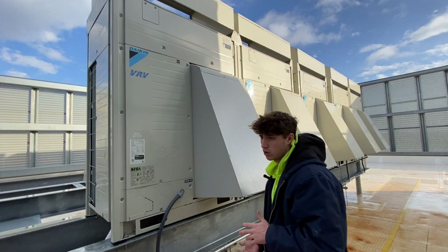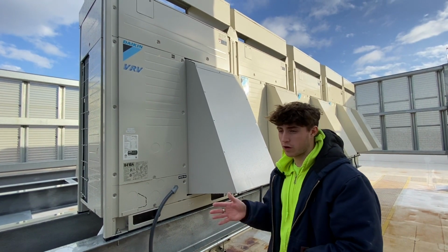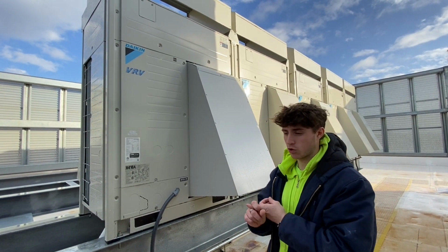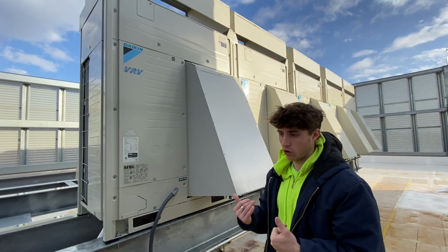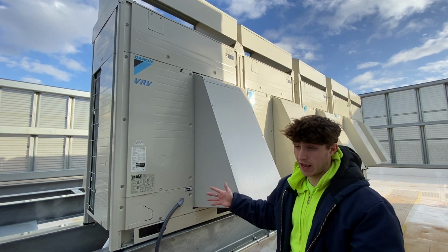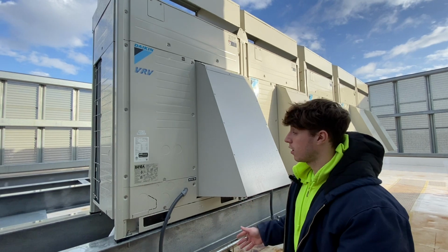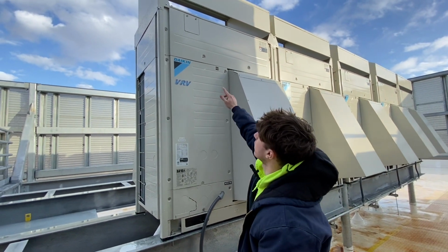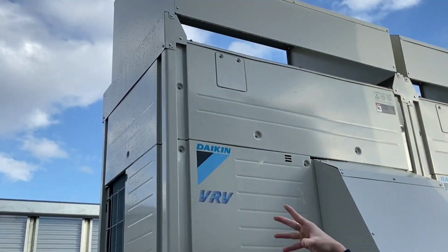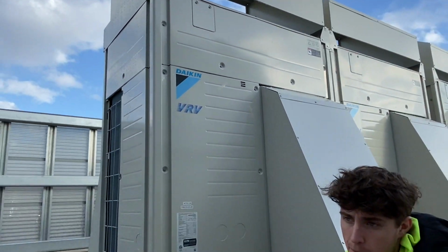If you had an incident where all the units downstairs were showing a U9 and not one of them was showing an actual true error code, a U9 means that there's something wrong with the unit, but not me. So there's something going on with one of the other units or the condenser itself that's having an issue. If all the indoor units are showing a U9, then my best bet would be to go up to the condenser out here and take off that little window right there, and there should be a black tab right behind that window that you should remove, and it will show you a little screen that you will see the error code that will pop up on there.